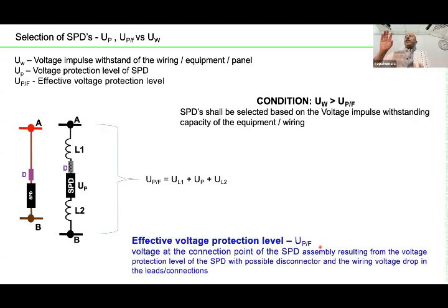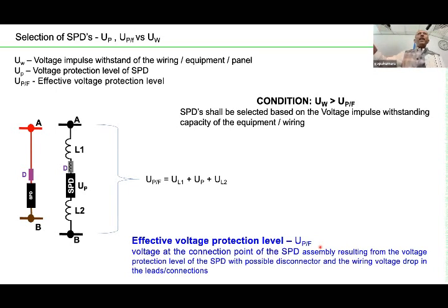Now, the ultimate purpose of putting the SPD is that the transient overvoltage between point A and B has to be limited to a very small level, because your equipment can withstand only, for example, 2.5 kV. Our aim is that between point A and B, the potential should be lower than 2.5 kV. Let's say 20% lower, so don't allow more than 2 kV.